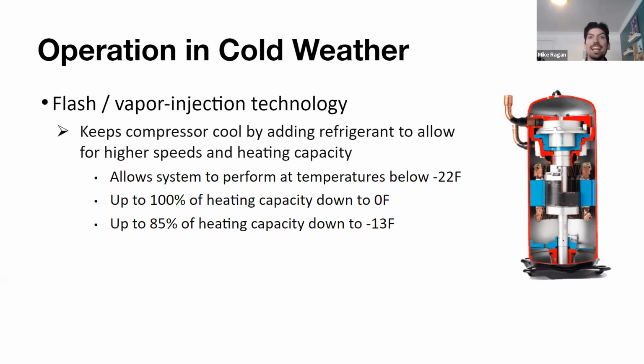So by adding that liquid refrigerant to that compressor, we don't need to worry about it overheating, so it can operate at a higher speed for longer periods of time without any worry of safety issues. This allows the system to perform at temperatures below -22 degrees. We get 100% of our heating capacity down to 0 degrees.